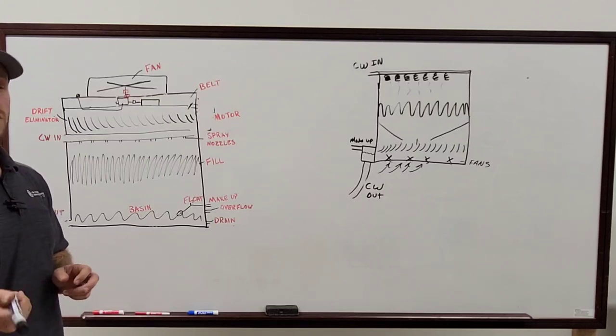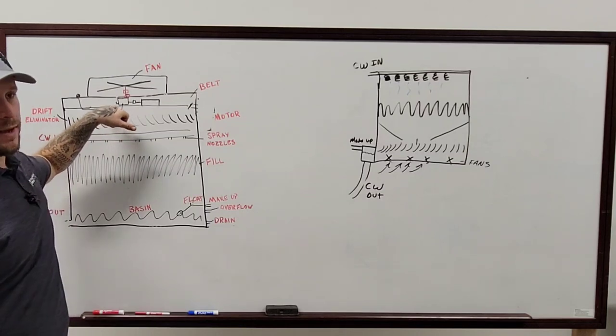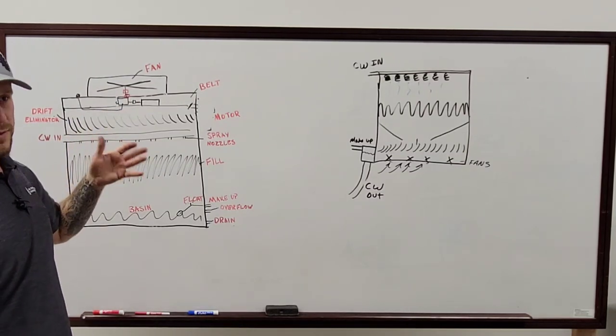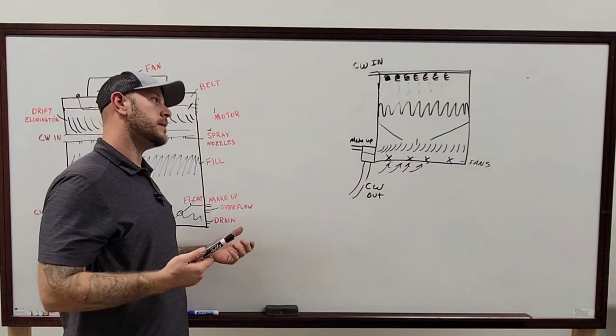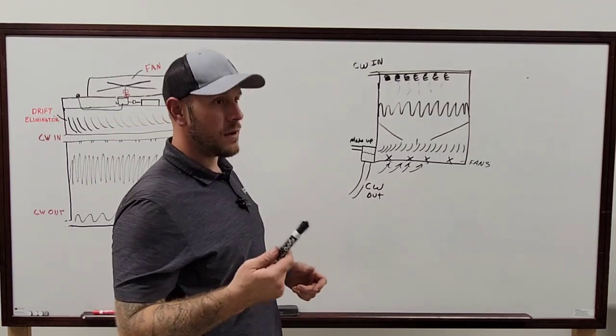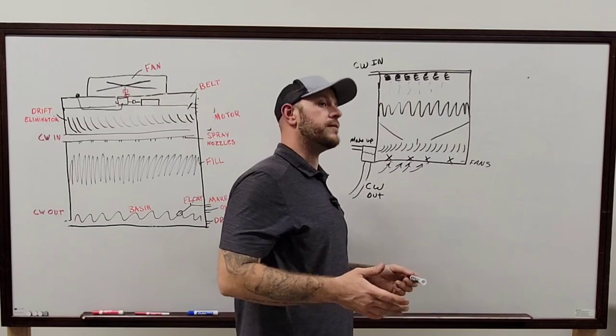And on some of the newer ones now, they even have a drain in the line where you can open that up to drain some of the oil out to test for something that you think might be going on inside of there. Just because there's metal shavings in there doesn't mean you'd be able to physically hear whatever's grinding or going on in there. So they give you a way to test for that.